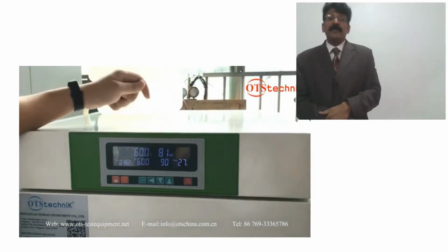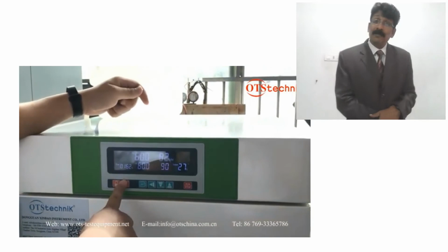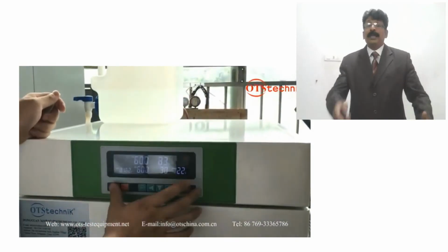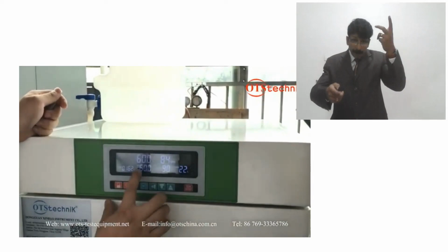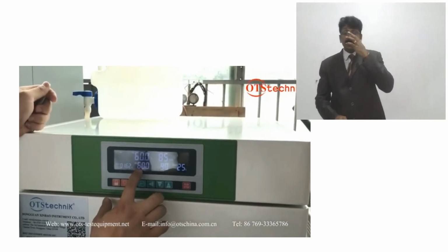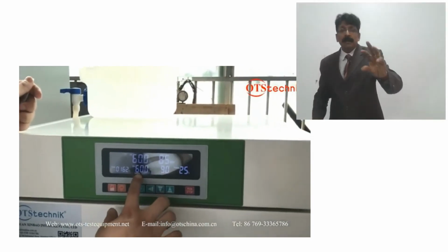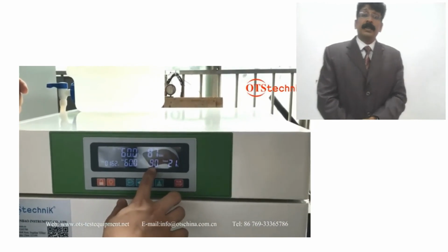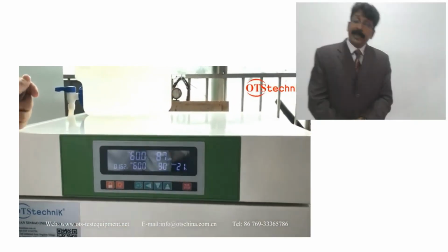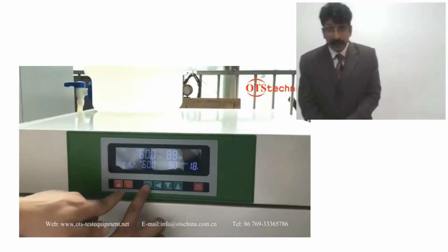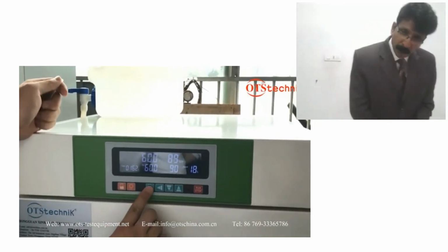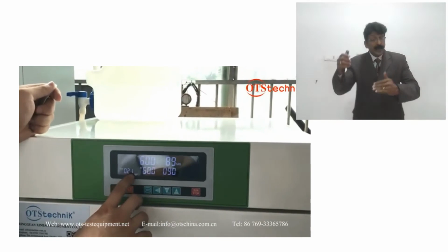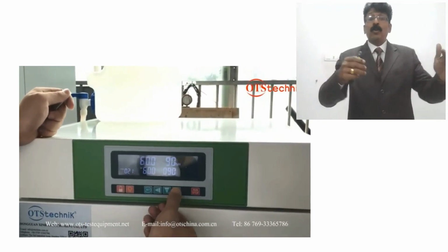Even for a stability study we need humidity, and it takes some time for the water to be maintained for the humidity. It is kept there in the tank, and there is distilled water, and the humidity can be analyzed by means of testing. We can set it according to the humidity range. First they will keep it at maximum, then at the lower level of humidity, and they will maintain the temperature also, so that we can find out whether the instrument is working in the proper way.